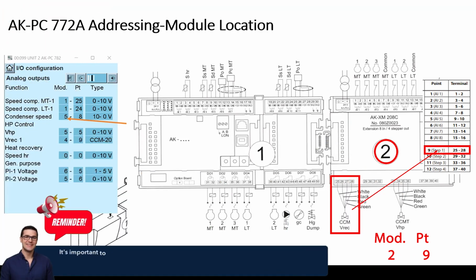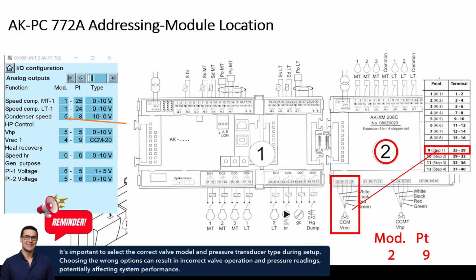Yeah, so you've got to take the insulation off the valve, because if there's insulation on it, you've got to look at it and see if it's a CCM 20 as we have there, or another one, a 12 or whatever you have for those, and you just select that to make sure. Because if you put the wrong one in there, that's going to have a different range. It's going to have a different step rate. Yep, there are different max steps, and now you think you're driving the valve 100% open, and you've only driven it maybe 75% open.